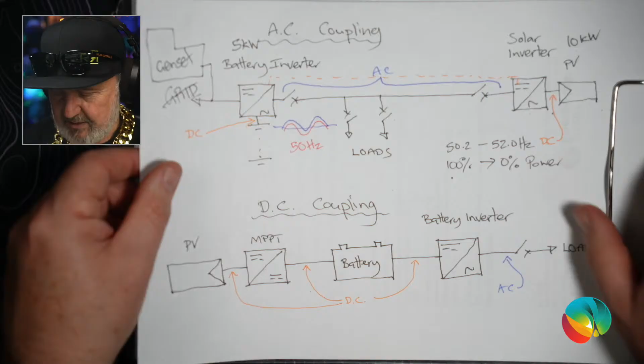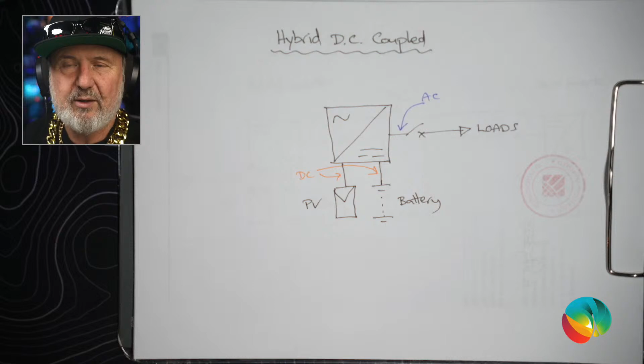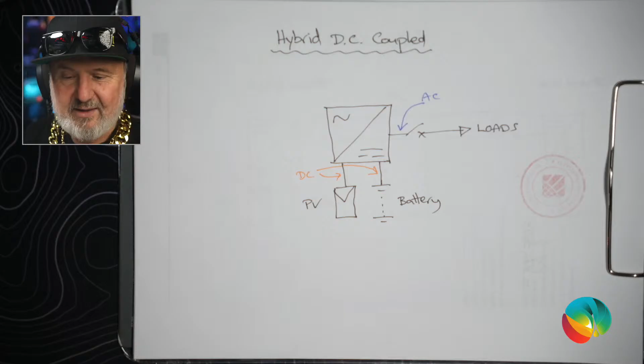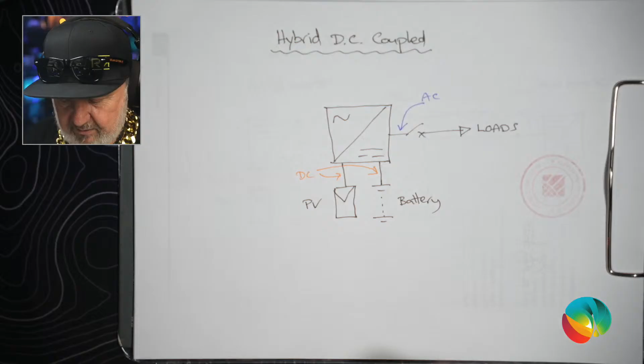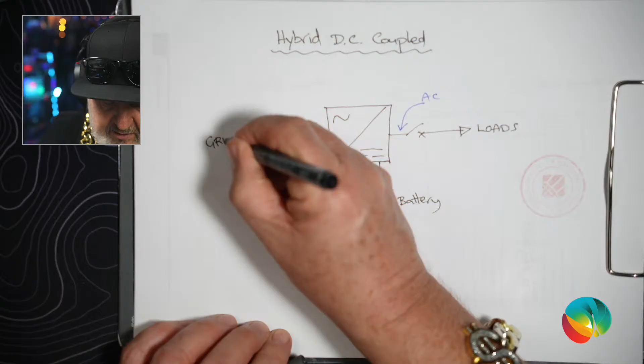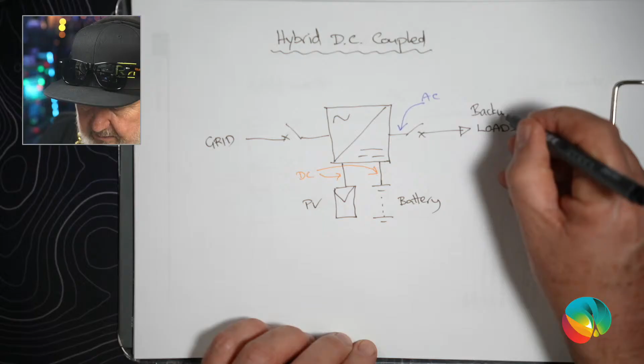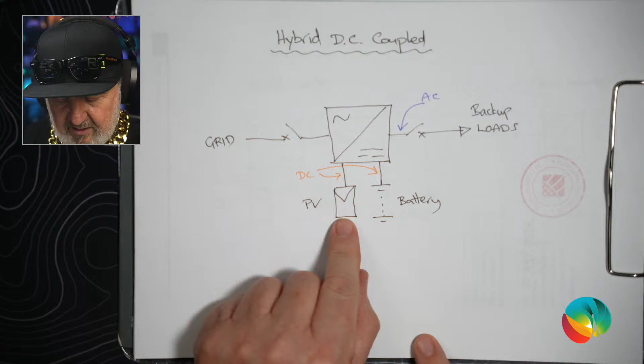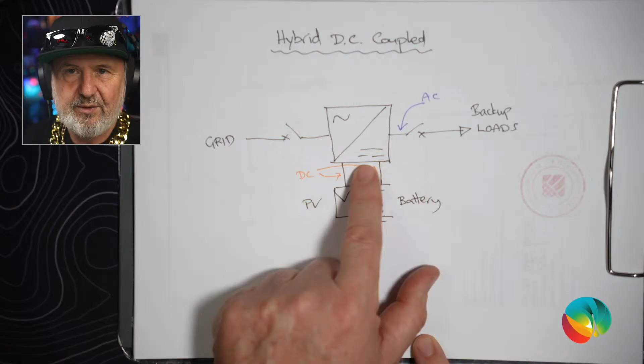Now let me make it a little more complicated. Why don't we do DC coupling but all in one device? So what you're looking at here is what's commonly referred to as a hybrid inverter. So it can have solar connection, battery connection, and loads. And most often, it will also have a grid connection as well. So there's our grid, and we could call this backup loads. Now, internally, it's DC coupled. That means the DC power from the solar panels is going directly to the batteries via an internal voltage current matching conversion. So it doesn't get converted to AC until you want to use some energy. That's when the AC gets created.